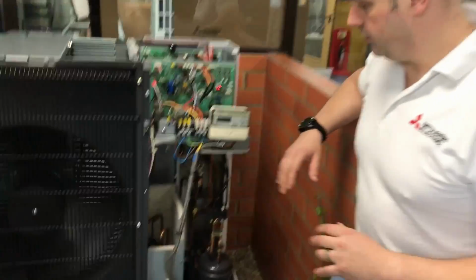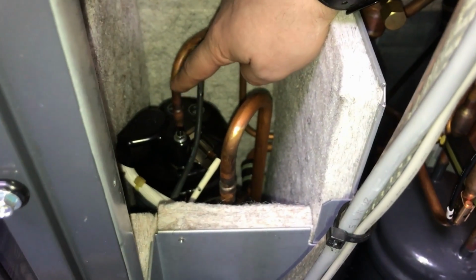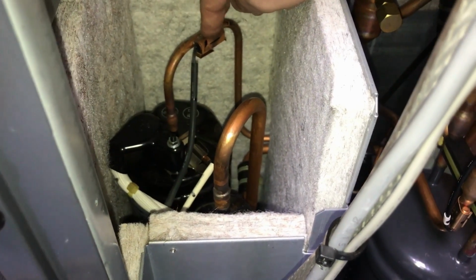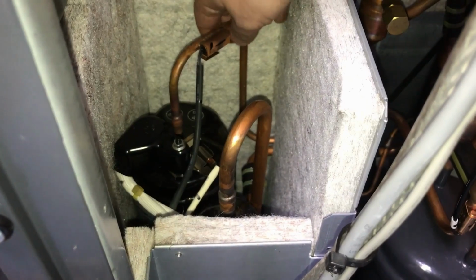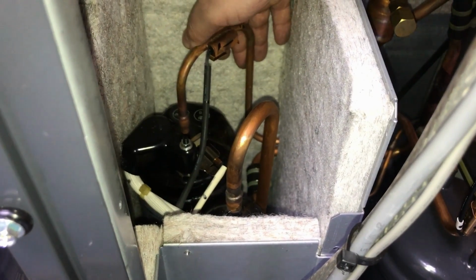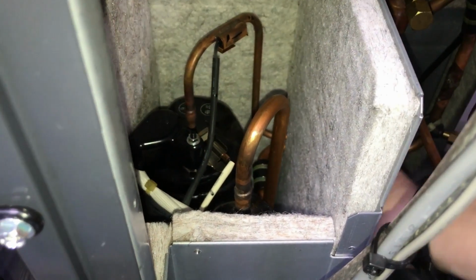The Ecodan unit is running in heating or hot water, so normal operation. I'm going to start off with the compressor. The refrigerant's coming off the top of that compressor. There's my discharge pipework, and that's being measured there on TH4. And that nice hot vapour heads off from there, so it's nice and warm, and it leaves from there.